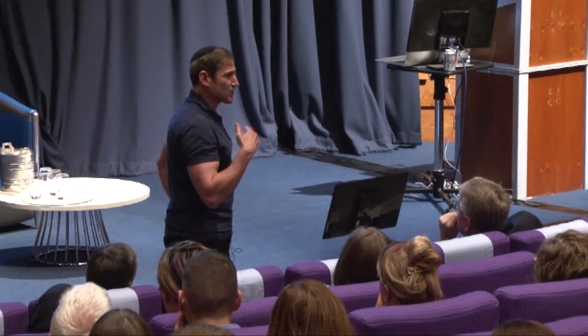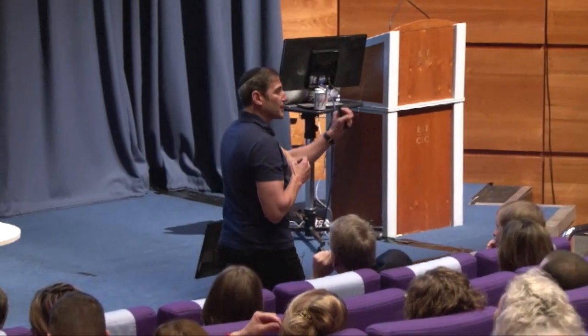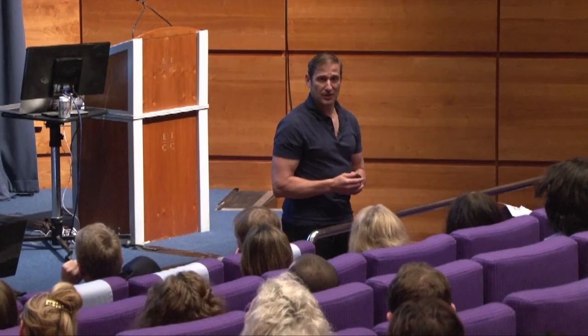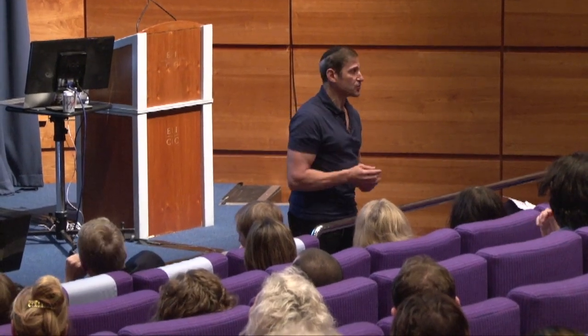Interesting bit of trivia, it's not the tip that heats up at all. It's microns away, right past the tip where the E fields concentrate in the tissue. That's where the burn is likely to occur, and that's what happened with this gentleman as well.